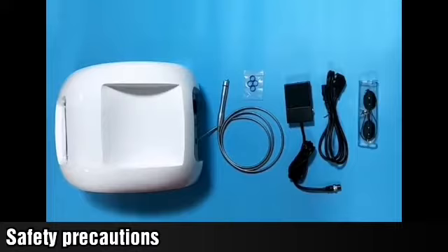Second, instruments belong to precision instruments. We should cherish the optical fibers. We can't pull hard and should handle it lightly. The handle has a precise optical system. Don't work hard. Third, don't use too much power to avoid scalding. Fourth, the instrument should not work against inflammable, explosive, and other dangerous goods. Don't use too much energy when testing on paper to avoid smoking and contaminating the lenses.